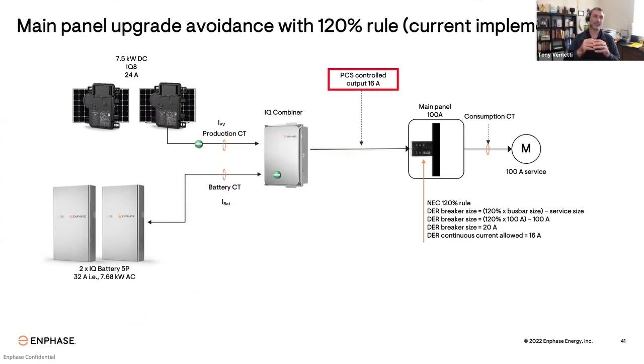Now let's say the system is in California with a net billing tariff, and the customer wants to have two 5P batteries to sell energy back to the grid. Those two batteries have an output of 32 amps. And again, the PCS limit here is 16 amps. That means the batteries aren't going to be able to discharge back to the grid at their maximum speed during that high value period. So the customer is not going to save as much money as they potentially could with this limitation.